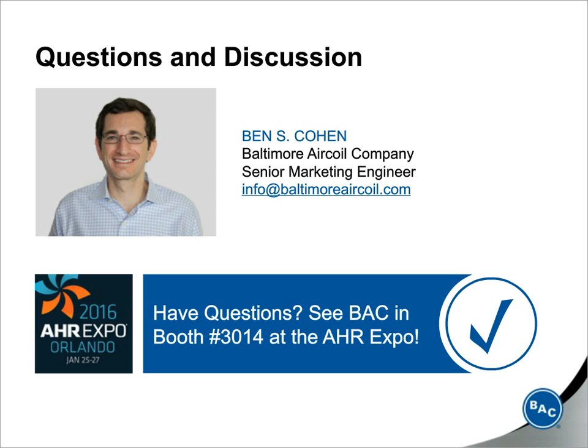Okay, and a question on the direct drive fan systems. What's the price point of the direct drive fan system as compared to a conventional drive system? The price premium really depends on the motor size and the unit capacity. While there's maybe not a specific answer to that, it generally provides a payback of less than 4 years in energy savings and reduced maintenance costs when compared to a conventional belt or gear drive system.